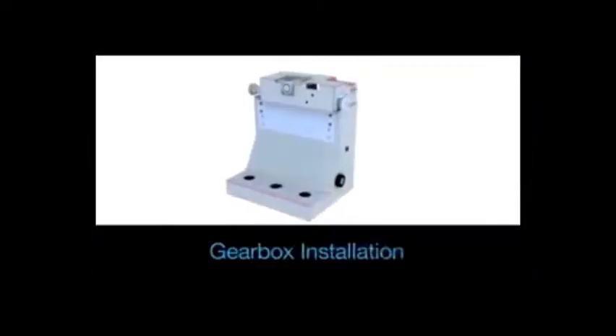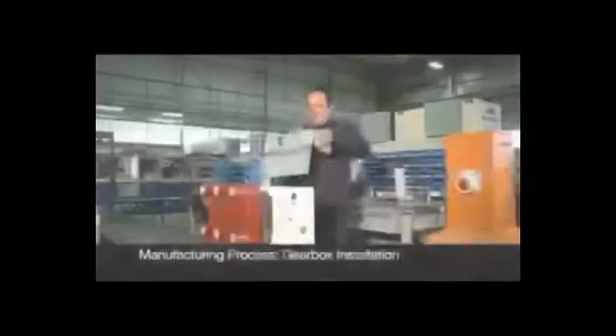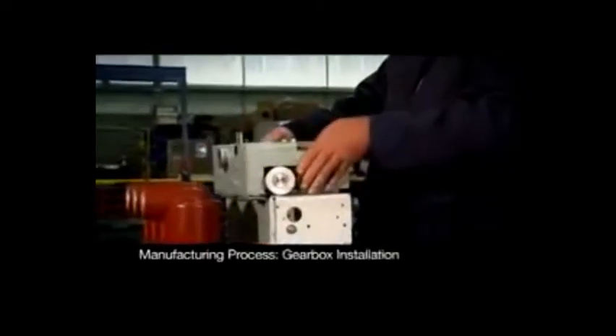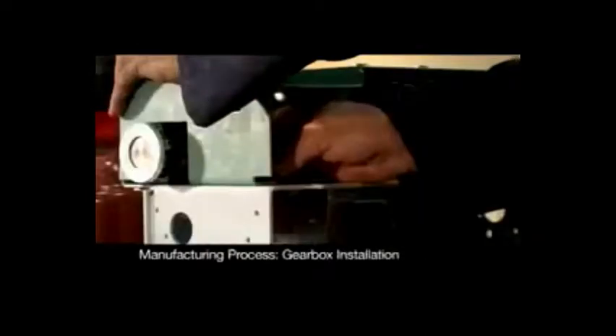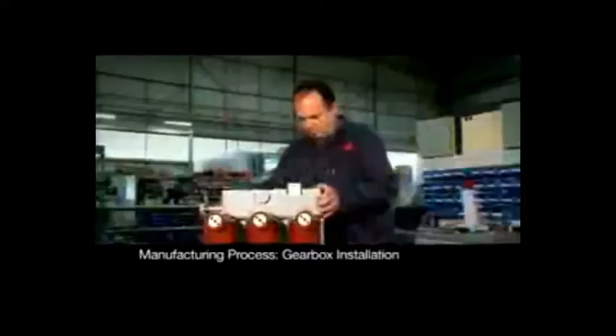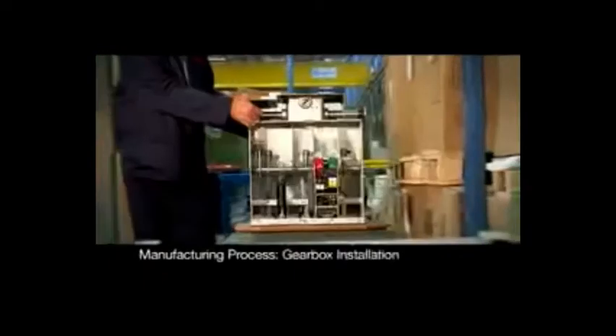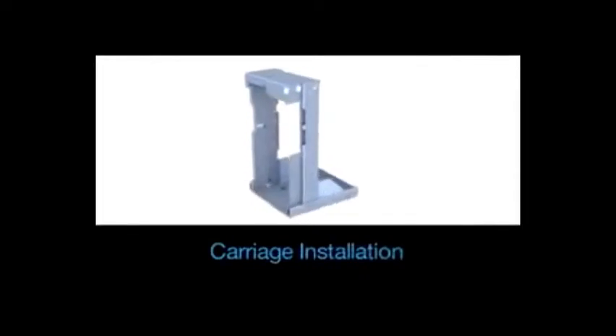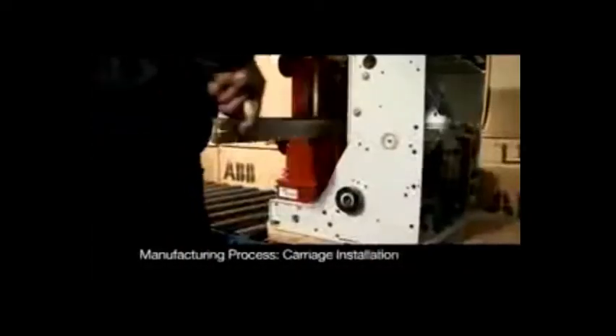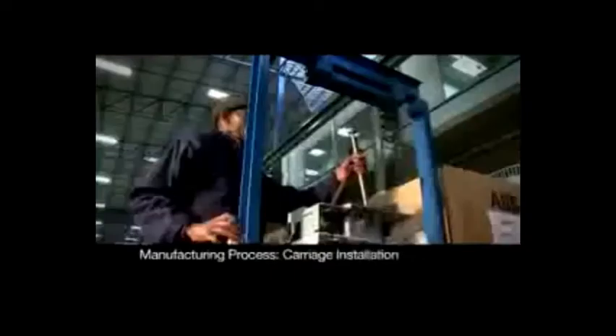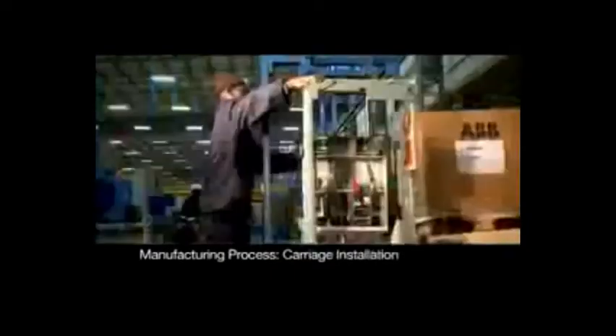We currently receive our VD4 and our HD4 basic units from Italy. These get imported to South Africa, where they then get machined locally. The unit gets sent out to a local engineering firm for machining. Once the machining is complete, the assembly process begins with the gearbox being fitted onto the unit. Here the unit with the fitted gearbox gets raised and installed into the newly produced carriage.